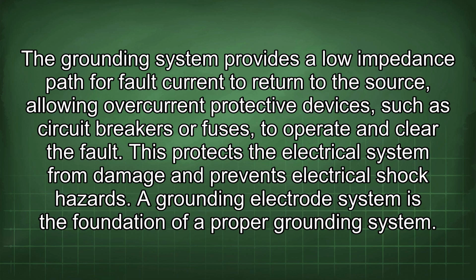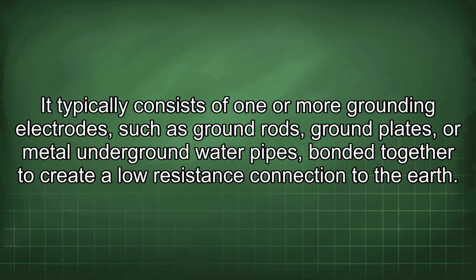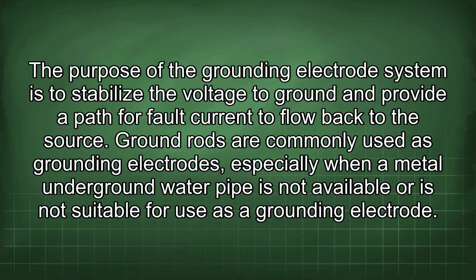A grounding electrode system is the foundation of a proper grounding system. It typically consists of 1 or more grounding electrodes, such as ground rods, ground plates, or metal underground water pipes bonded together to create a low-resistance connection to the earth. The purpose of the grounding electrode system is to stabilize the voltage to ground and provide a path for fault current to flow back to the source.